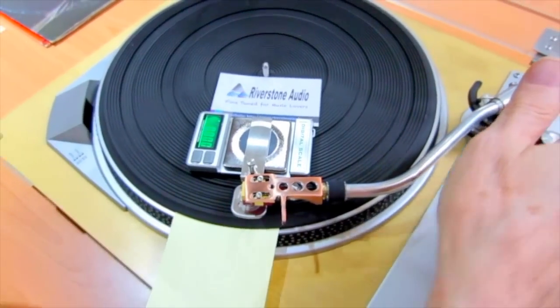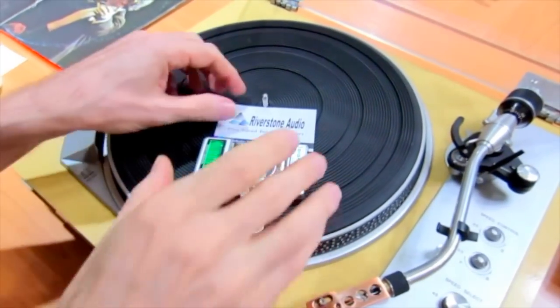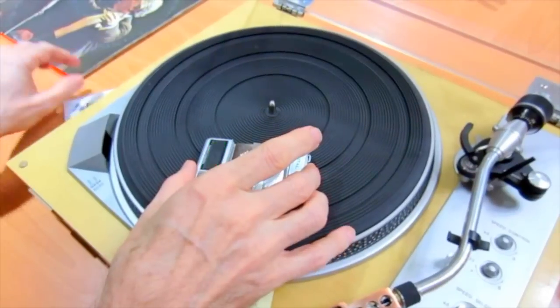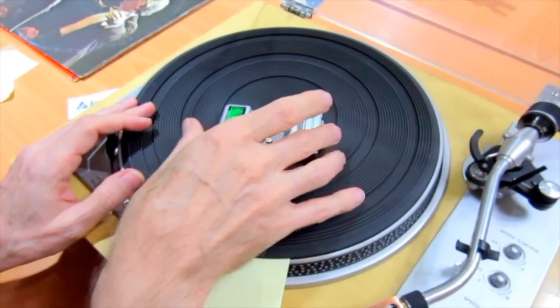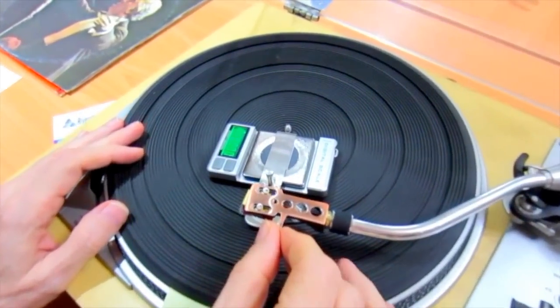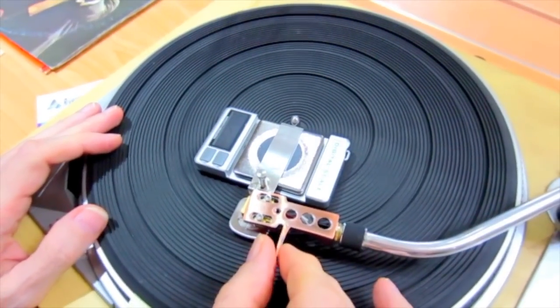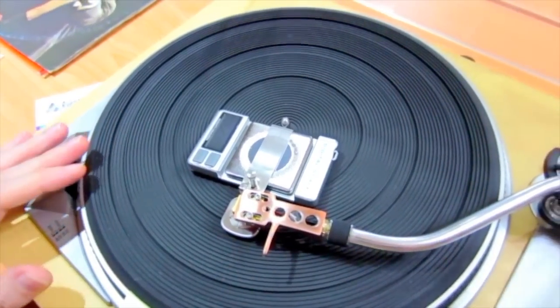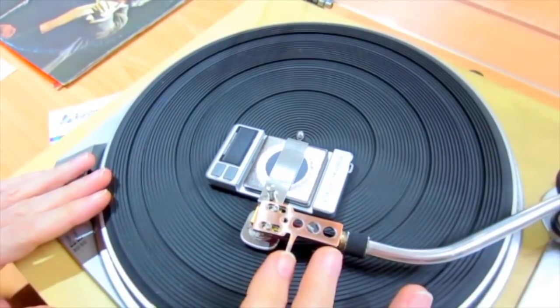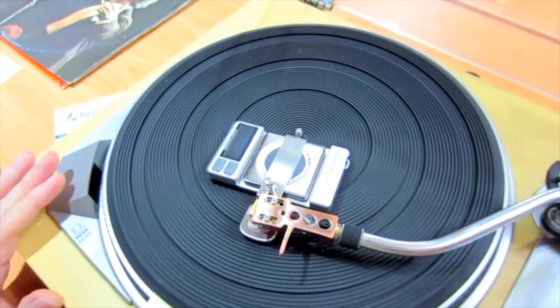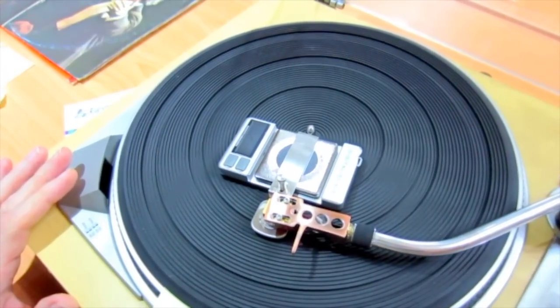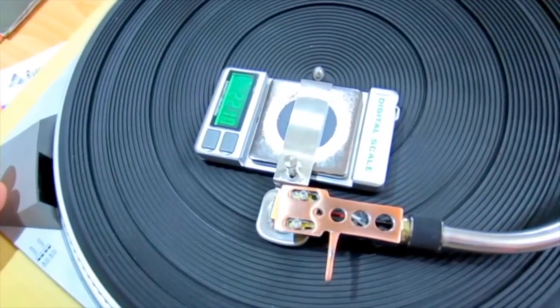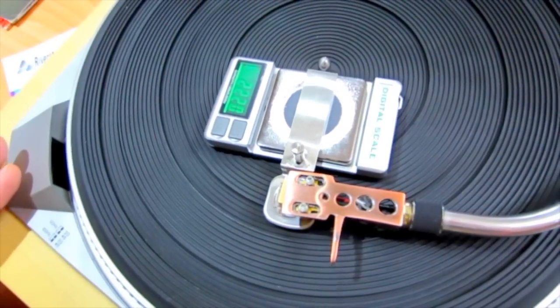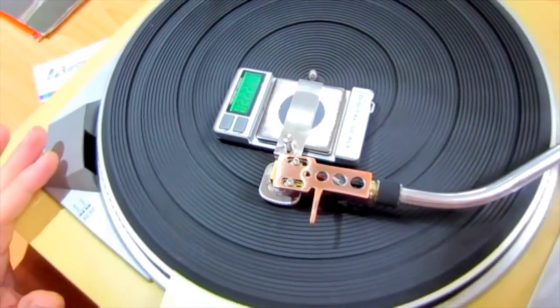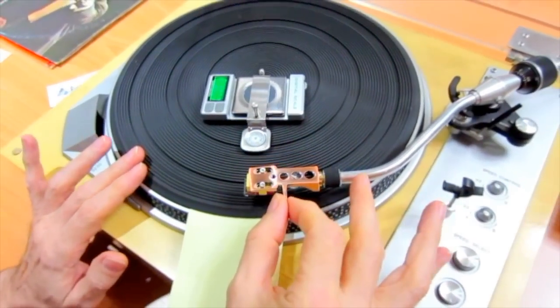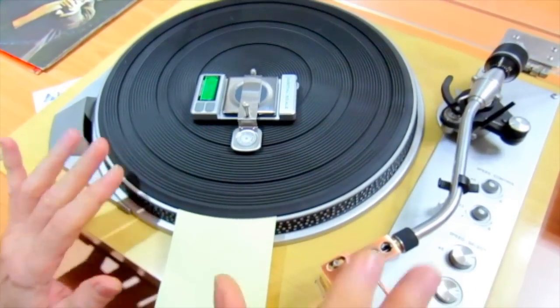Now, as I mentioned earlier, with radial position, you can get a different reading. So if I were to bring this in a little bit closer, and again, that's due to the different friction with different position of the bearing as I move the arm. And let me bring this down. All right, pretty darn close. Again, this was a well-maintained table. So I think the point is try to choose a consistent point where you take the measurement.